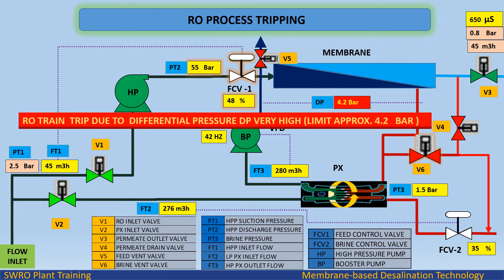RO train trip due to differential pressure DP very high, limit approximately 4.2 bar.